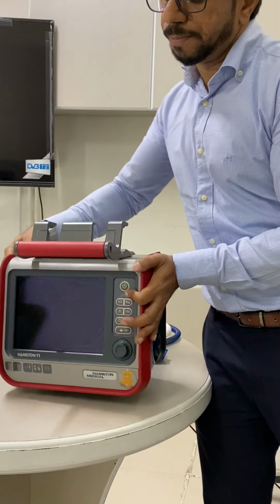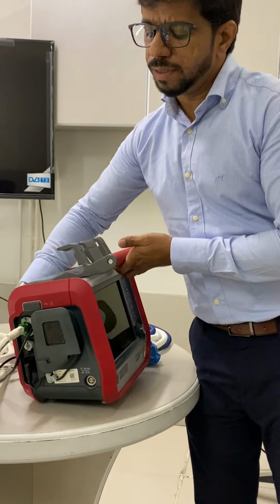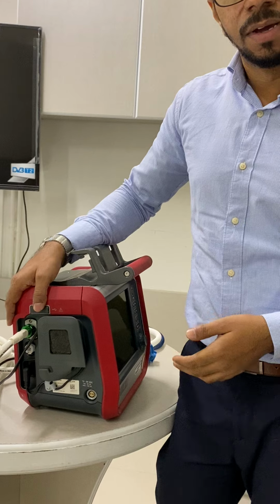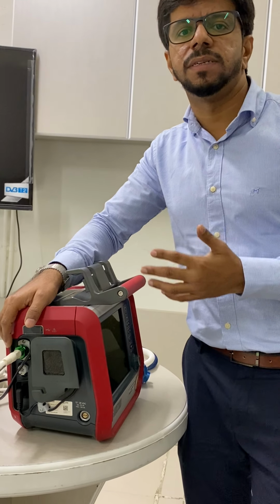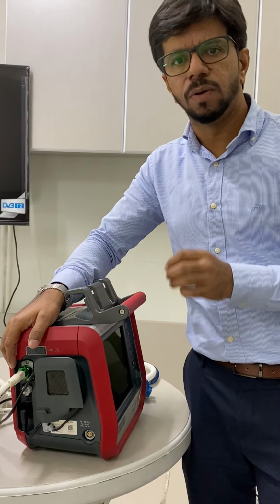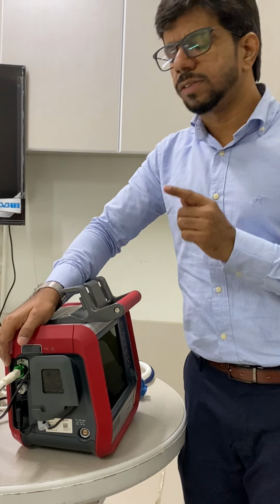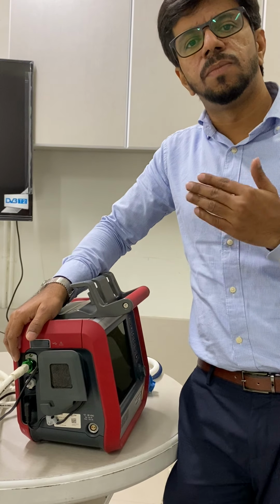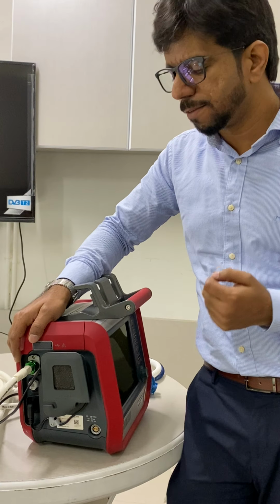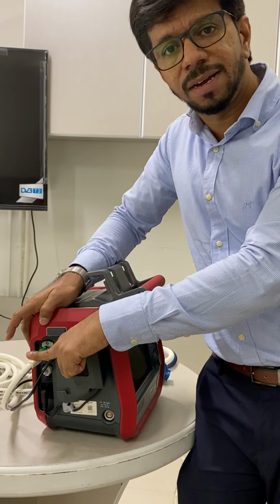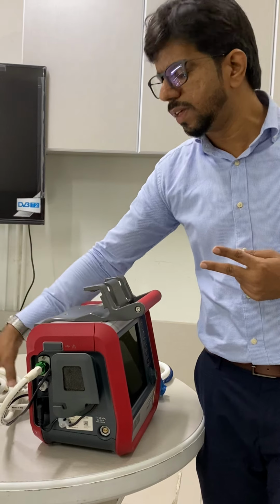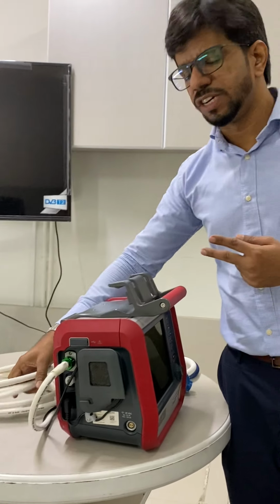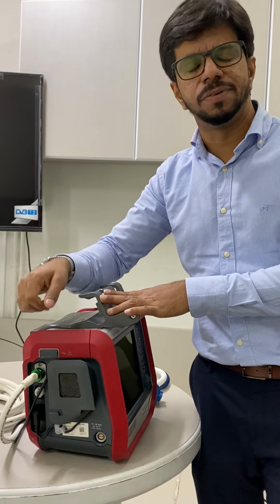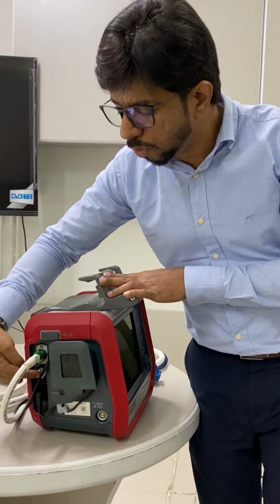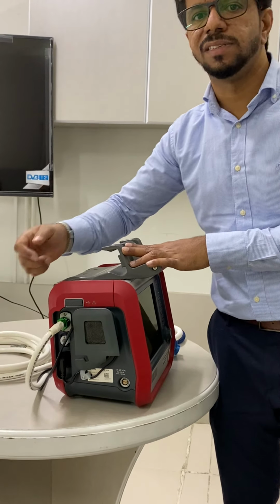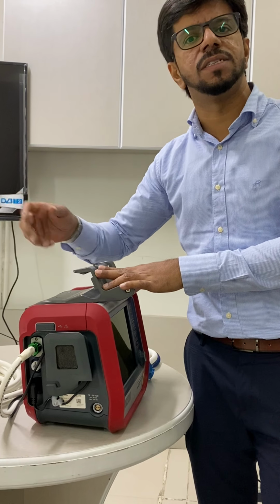From the other side we have the gas connection outlet. This machine is designed with turbine technology, so you don't need medical air, you only need oxygen, and only if the patient requires more than 21% oxygen. We have the oxygen supply in two ways. Either you can use high pressure oxygen, from the central supply or from a cylinder with a high pressure regulator, or you can go with low pressure. Low pressure is a cylinder with a flow meter, where you can adjust the flow.